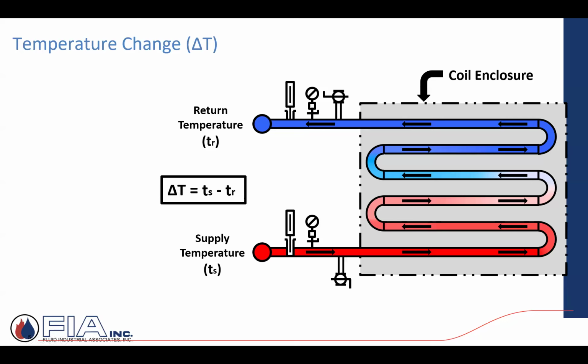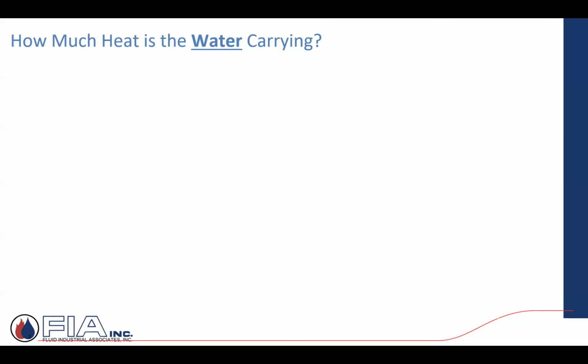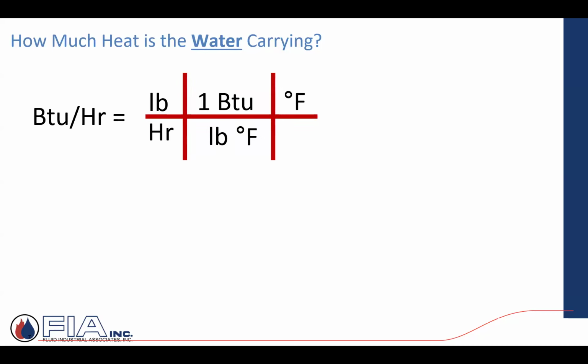A fairly standard number, which we'll reference as we move forward and that you'll hear throughout this and typically a lot of times in the industry, is a 20-degree delta T for heating loads. Supply it at 180, comes out at 160. Goes in at 200, comes out at 180. Not written in stone, doesn't have to be, but it's a very safe, very standard number for heating. So how much heat is the water carrying? And now we're getting into kind of building that equation, if you will, BTUs per hour.